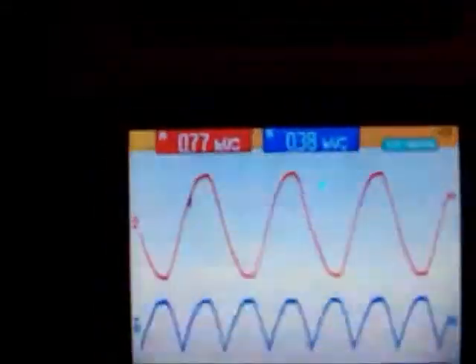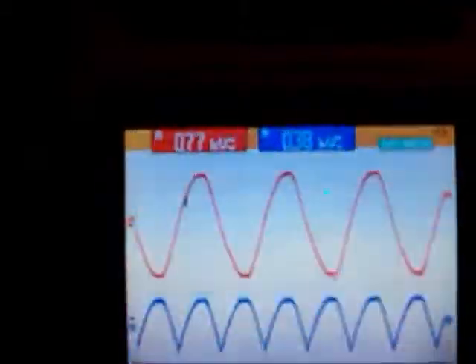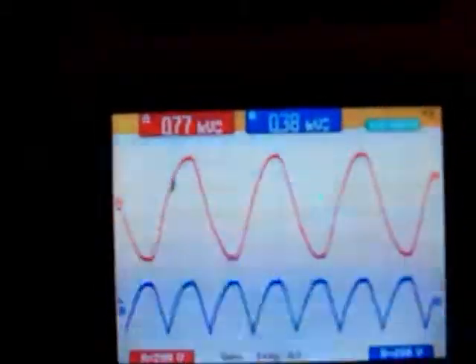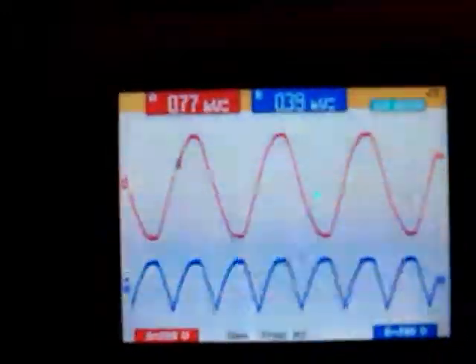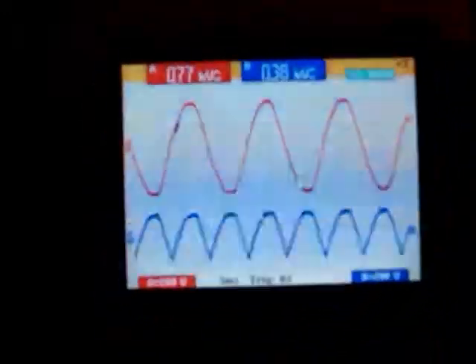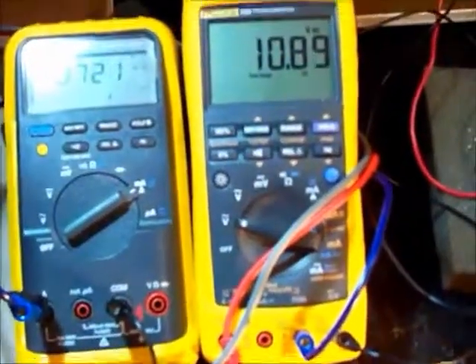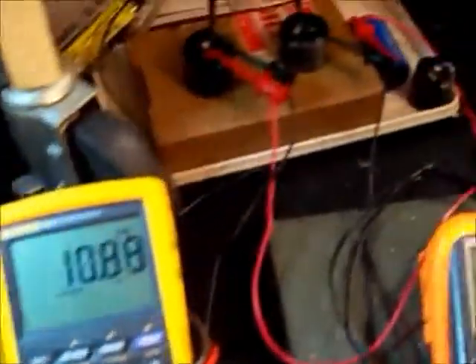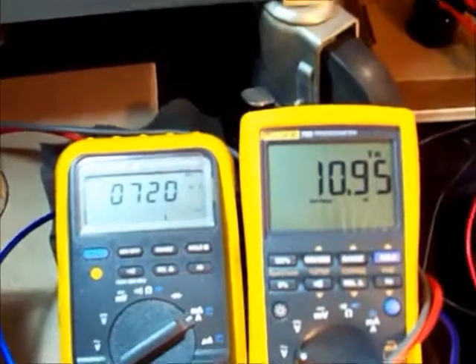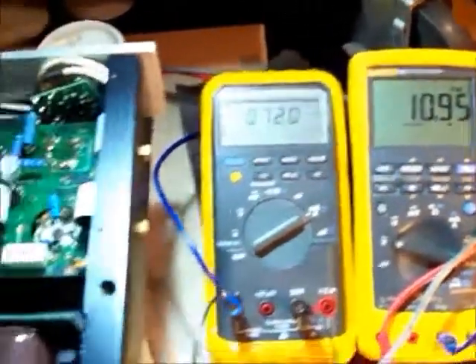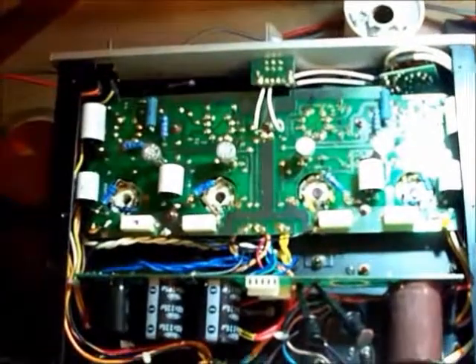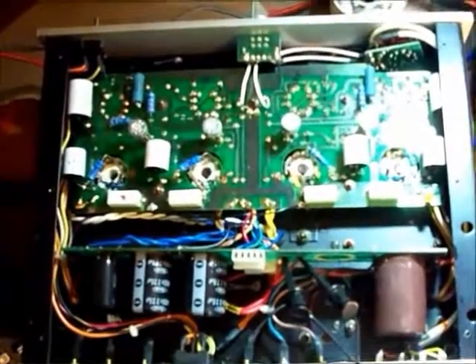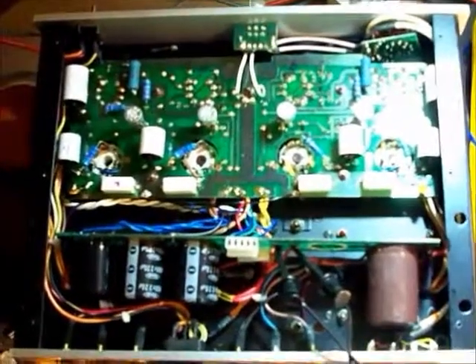Must be something going on there. Over here we've got 770 volts peak to peak, and 380 volts on the DC side. That 770 is the output of the transformer, which should be shown over here in RMS, but for some reason it has been disconnected. We probably got that clip disconnected. Anyhow, that's where we're at right now. We're going to probably come up with a plan B here and move this down the road.